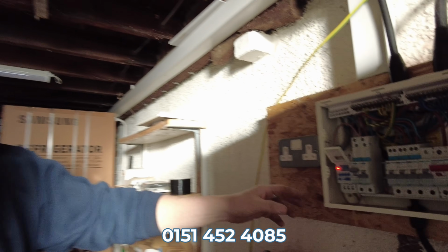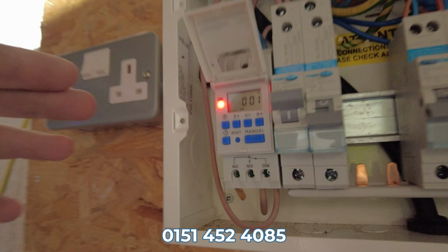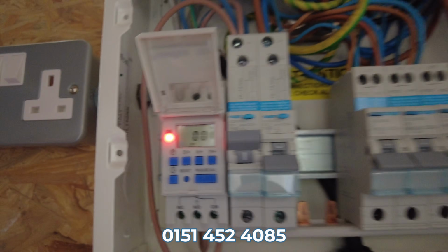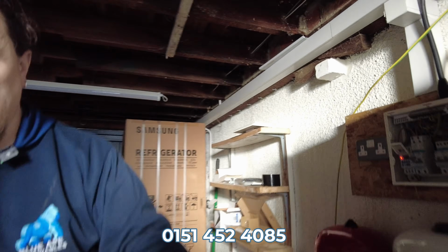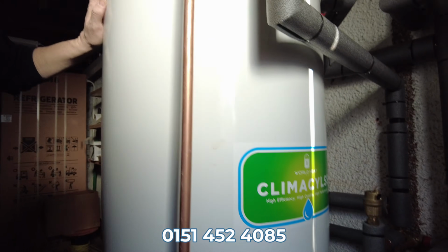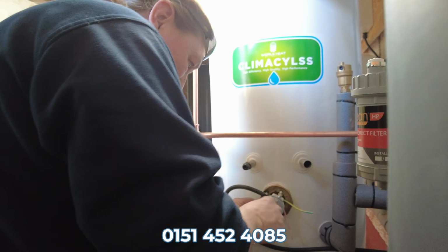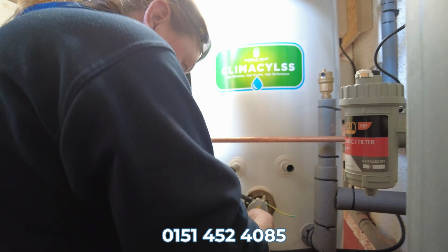So we're just testing the immersion heater for the Legionella cycle. The RCBO's on. We're just testing that the timer works properly. We'll set it up later to run for an hour on the nighttime tariff once a week. And at this end, you can see we've got a 3 kilowatt immersion heater here set to 70 Celsius. So we're just checking to make sure it warms the water properly. We're finished on the immersion heater and the timer for the Legionella cycle.